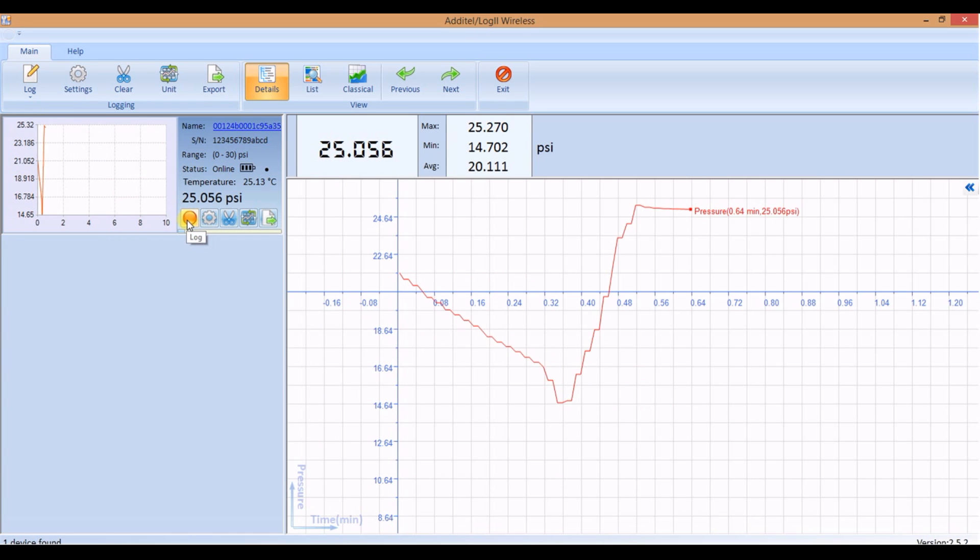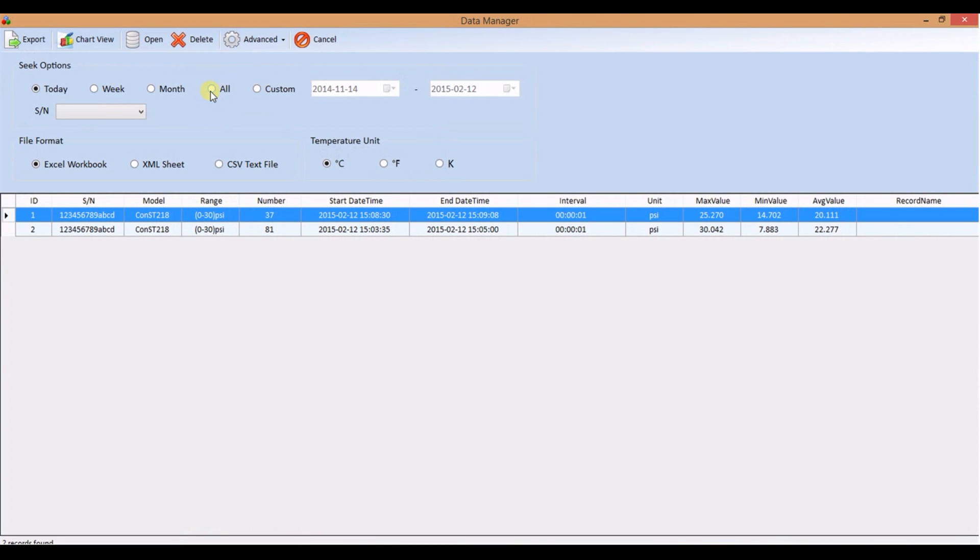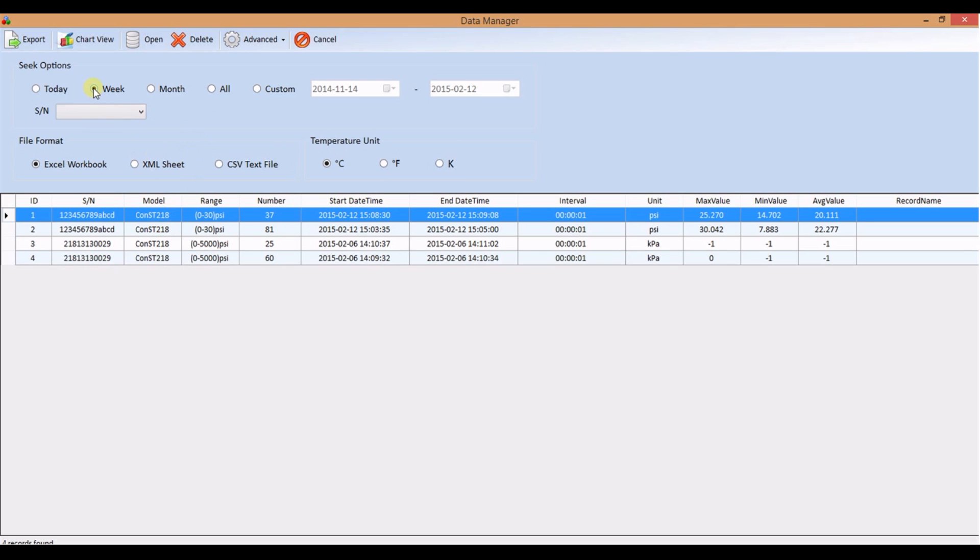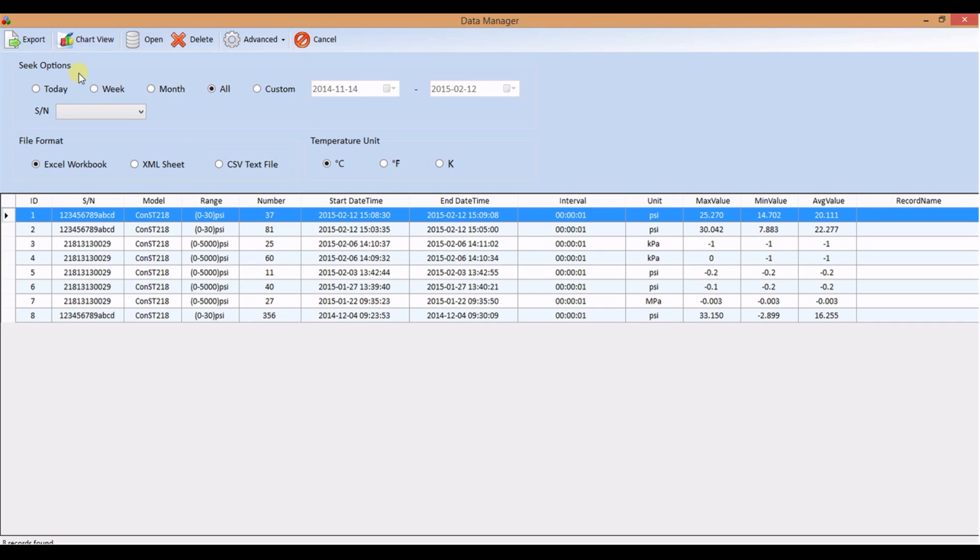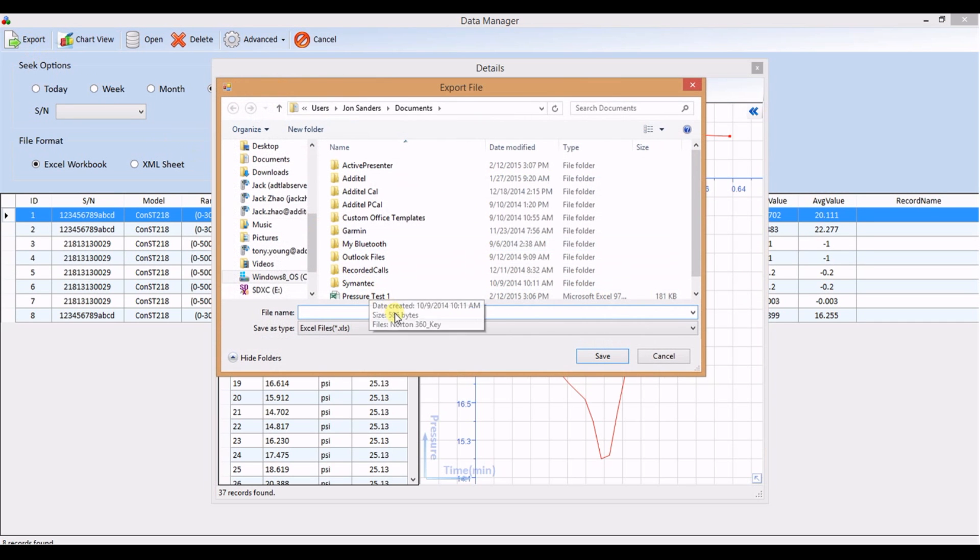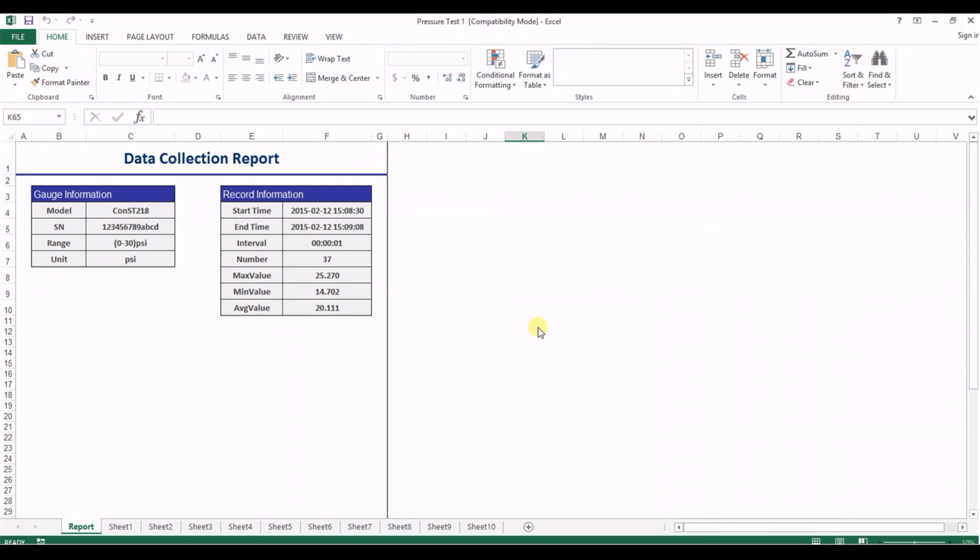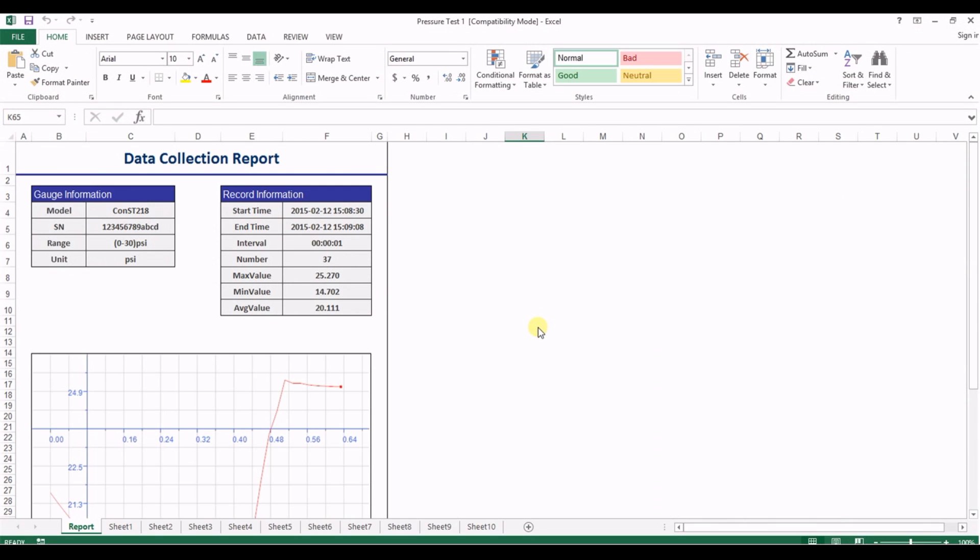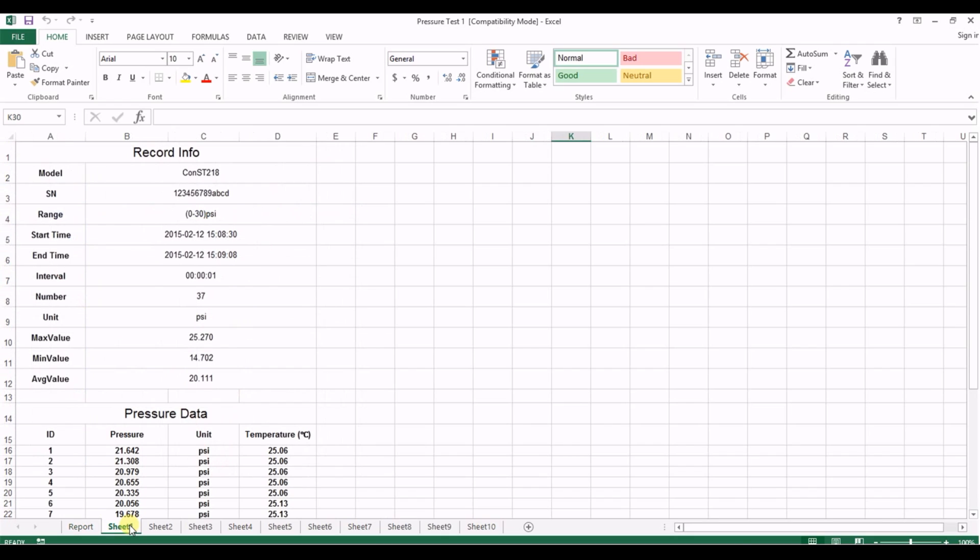To export stop the logging session and press export. You can select logging sessions to be exported based on the date range. Files can be exported as an excel or xml or csv file. When exported as an excel file, a report with a graph is on the first tab and raw data populates the other tabs.